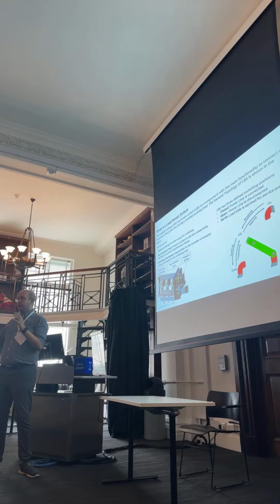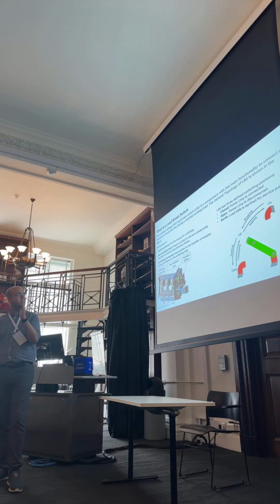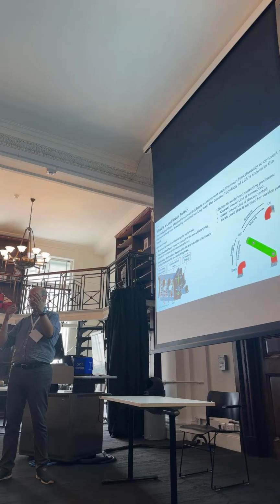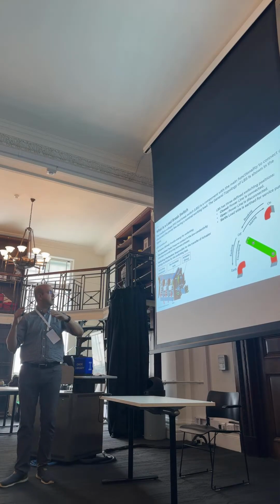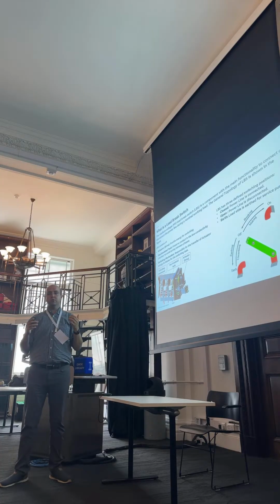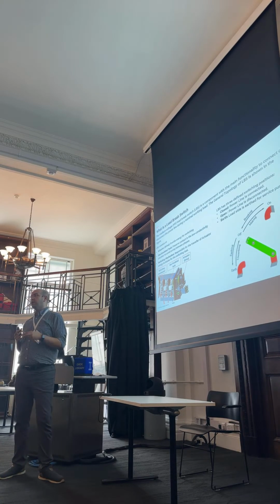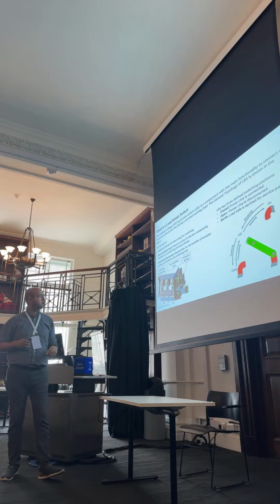It needs to make sure that between the poles, the three phases that we have, we don't have any electrical jumping, or in this case partial discharge. Due to the phase shift of the voltage, we might have electrons jump from one pole to another pole. So this gas should act as some form of dielectric to make sure that this behavior couldn't happen. And also, due to the passing of such high current and voltage through the line, we have a lot of Joule heating. So the atmosphere can easily get to 100 degrees inside this tank. So it also should have a good thermal capacity to not expand so much. Otherwise, this tank needs to hold a high pressure. So it's also quite important.